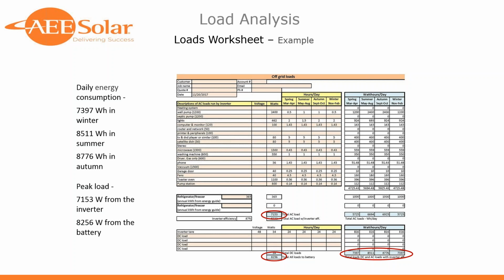And as Josh said, when you're looking at the maximum peak amount of power that you want to run, how many appliances all at the same time, you want to look at which ones are actually likely to be run at the same time rather than just adding them all up and ending up with an inverter that's too large. Things like you're not going to be running air conditioning and heating at the same time, obviously. Whereas your septic pump, your well pump, and your dishwasher may very well all be running at the same time. You may not be running a hair dryer and microwave at the same time, although it's potentially possible. Generally, when somebody's living off grid, hopefully they can keep in mind, in their daily use, maybe not to turn everything on at the same time. But that really only has to do with inverter sizing.